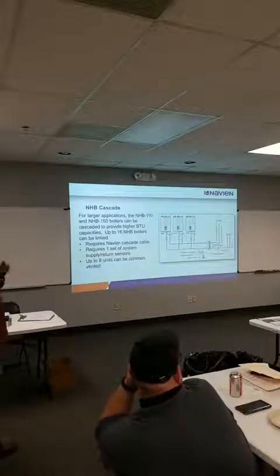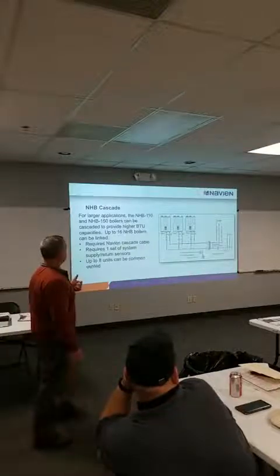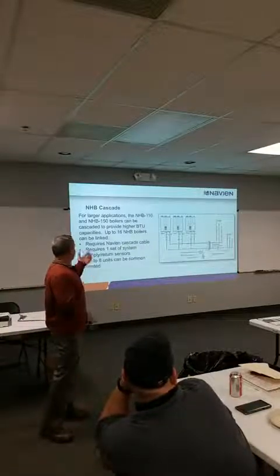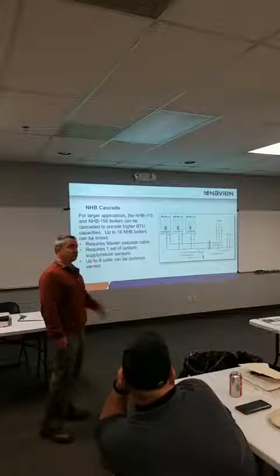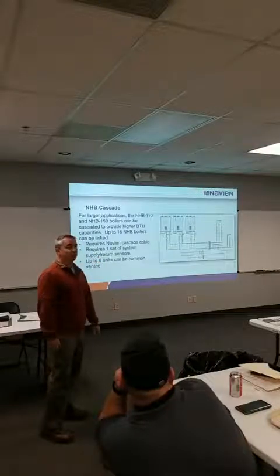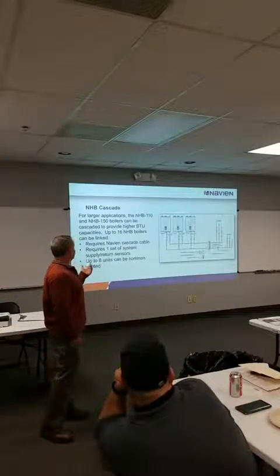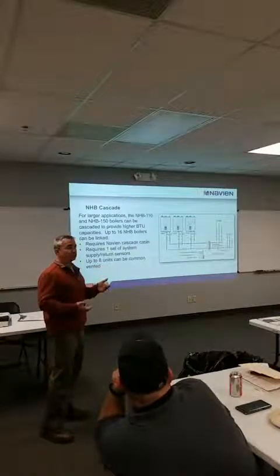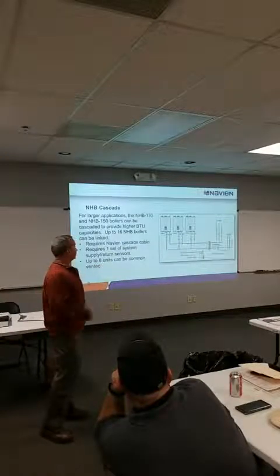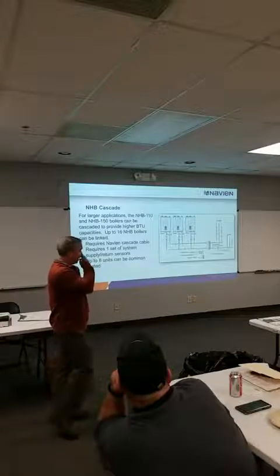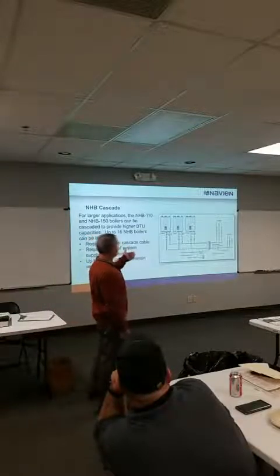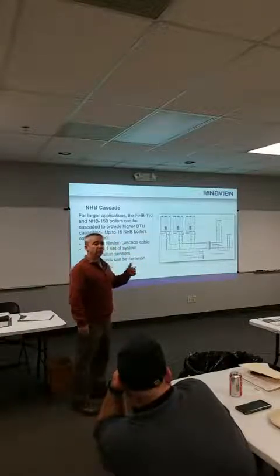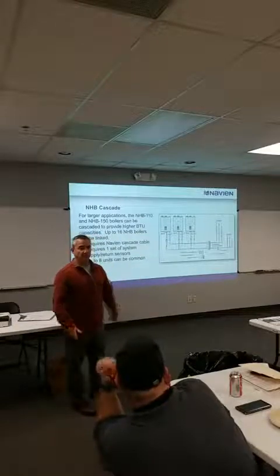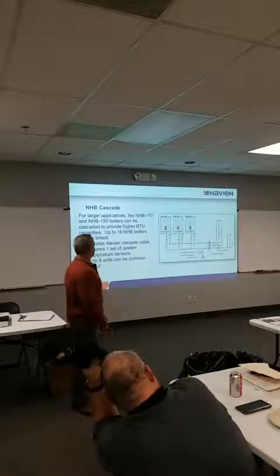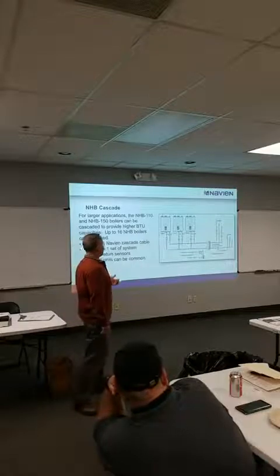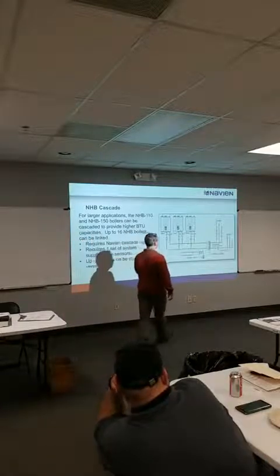And another thing nice with Navien is the first for a lot of stuff that Navien did, we can put up to 16 boilers per system. My commercial boiler, we can do up to 32. We can common vent up to 8 of these in a system. My commercial boilers, we can common vent up to 4. So we're unique in that manner. But your basic piping for doing multiple boilers is the same, we're not doing anything special with piping. You do need to buy these temperature sensors whenever you're doing multiple boilers.